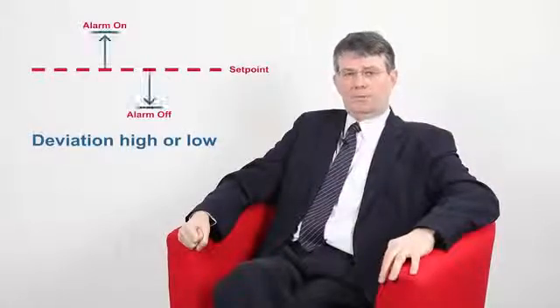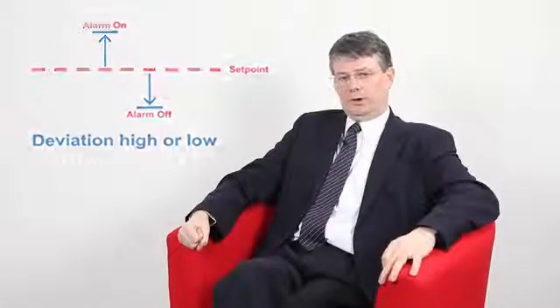For example, if the set point was set to 200 and a high deviation alarm was set at 5 degrees, it would activate at 205 degrees. A low deviation alarm with a value of perhaps minus 3 would activate at 197 degrees. If the set point was changed to 220 degrees, the activation points would be 225 and 217 degrees respectively.